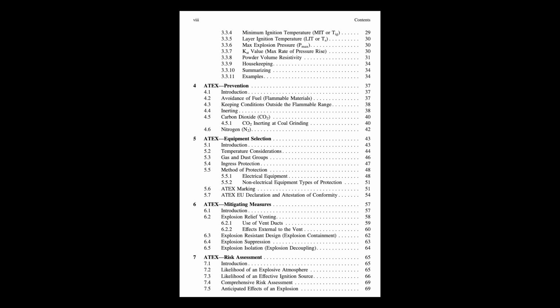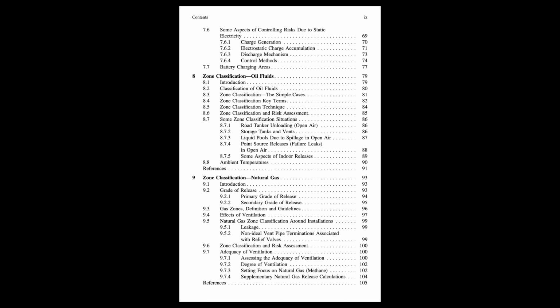Definitely not. The guide even touches on the calculations involved in sizing these vents, especially for dust explosions. You need to know things like the dust's Kst value, how strong the explosion could be, the maximum pressure the vessel can take, the vessel volume. It's proper engineering. Sounds complex. Okay, what's the second mitigation category?